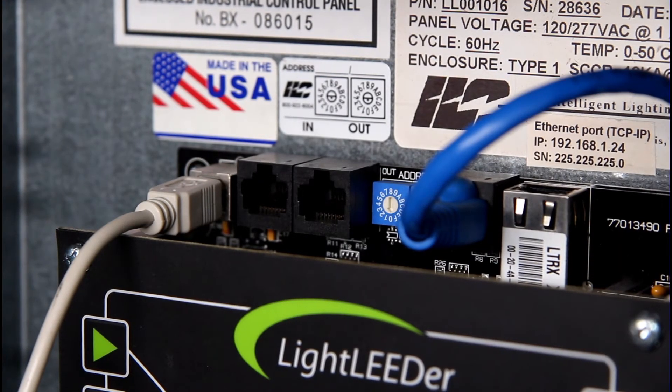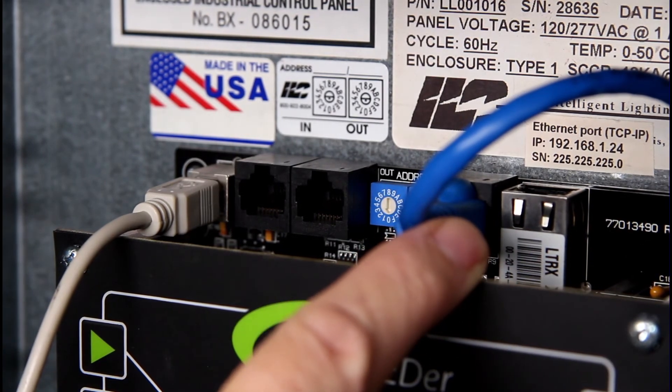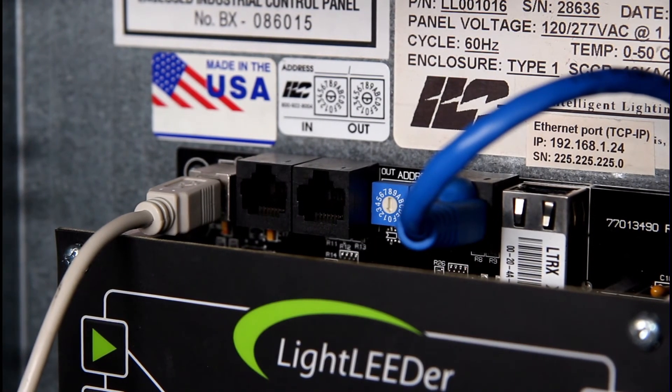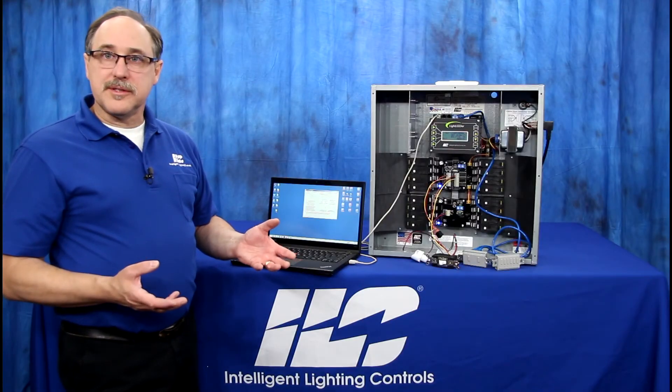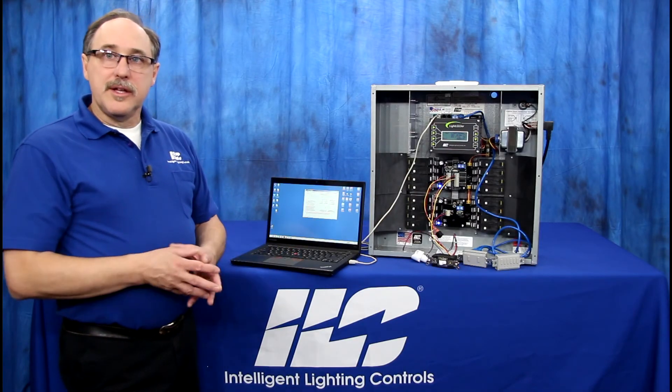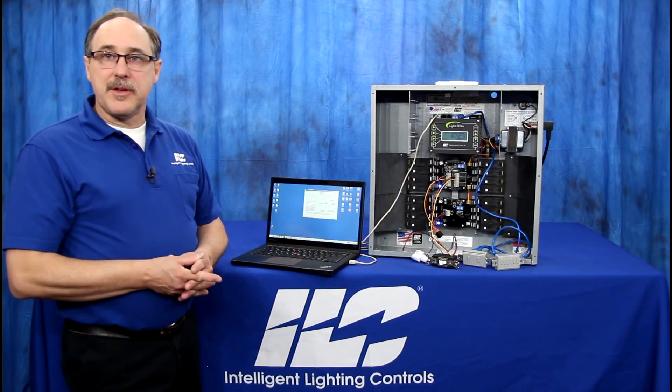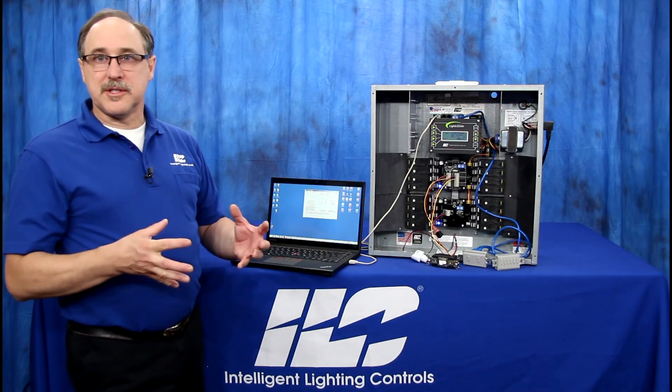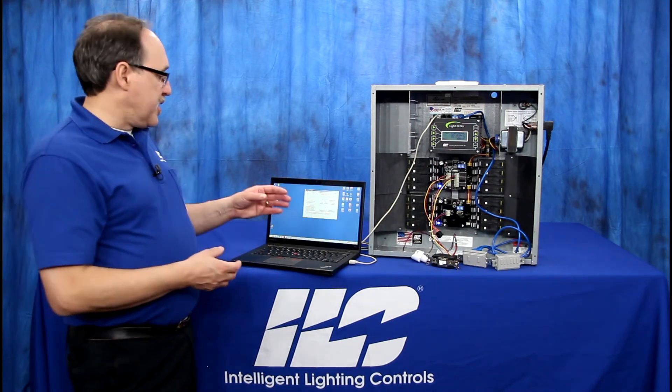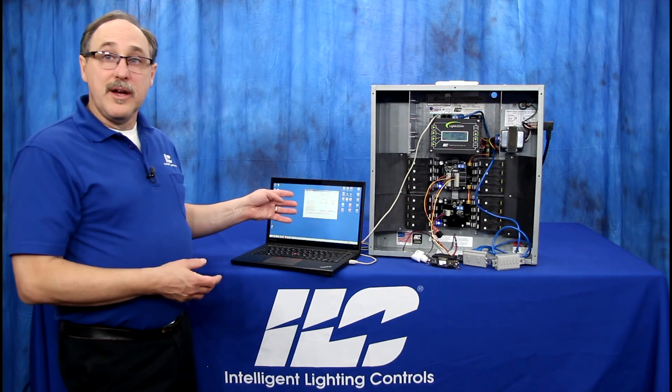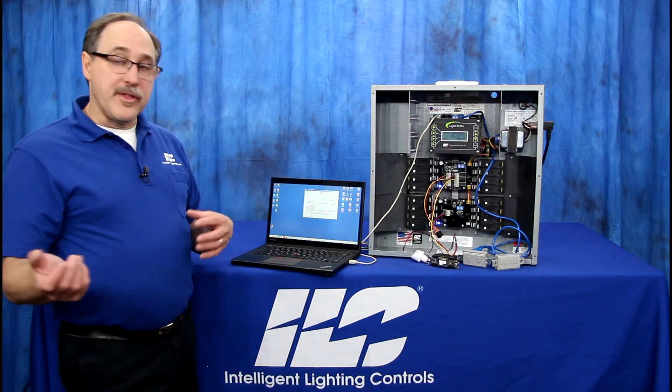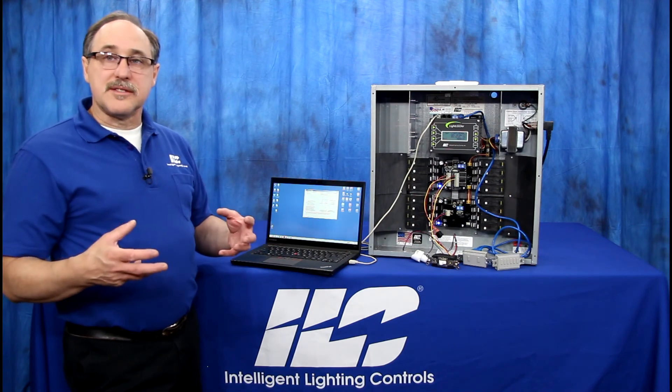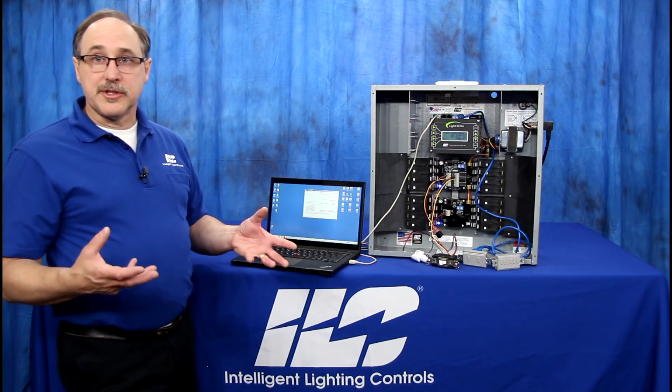You can go to the TCP/IP port on your panel if the panel has one. A lot of standalone panels don't have an IP port unless it's requested for the job type. If you have a network of systems or a network panel, typically the master panel in the network will have a TCP/IP port because on larger systems like that it's expected that the customer is going to load this software on their computer system and they're going to connect to it and make timer changes and things like that after you're gone and you're done with the job.